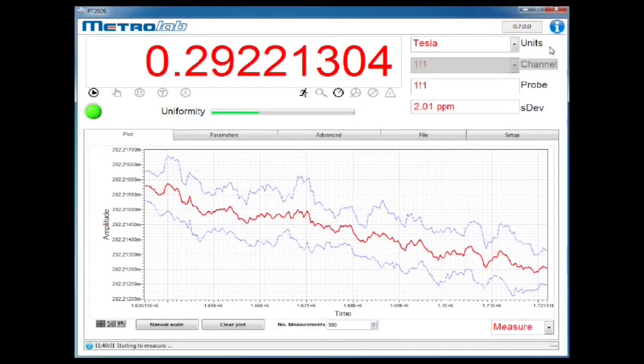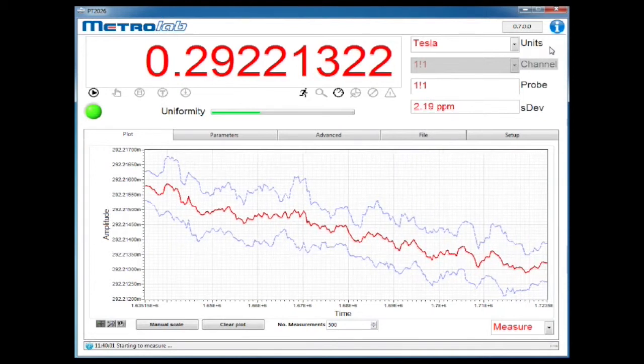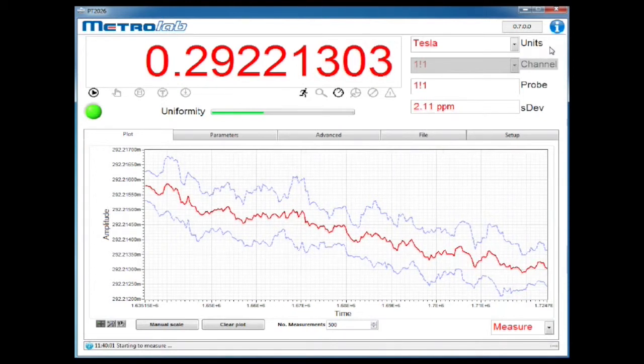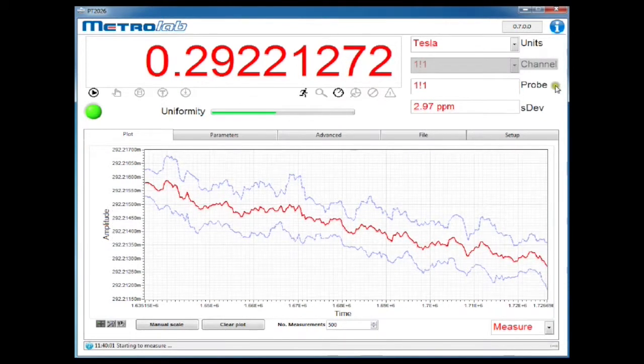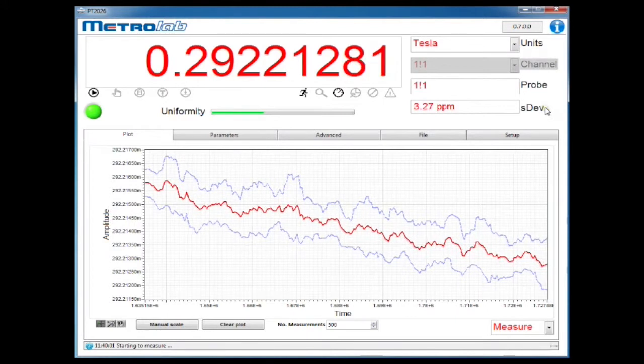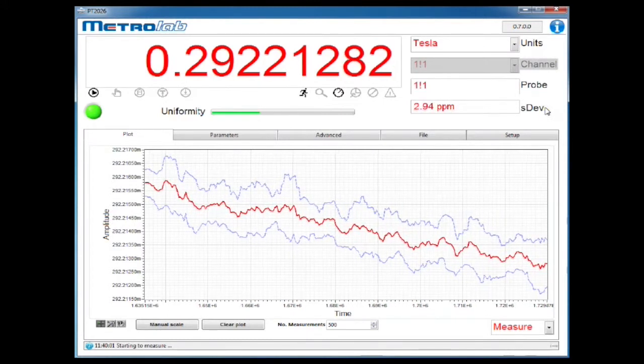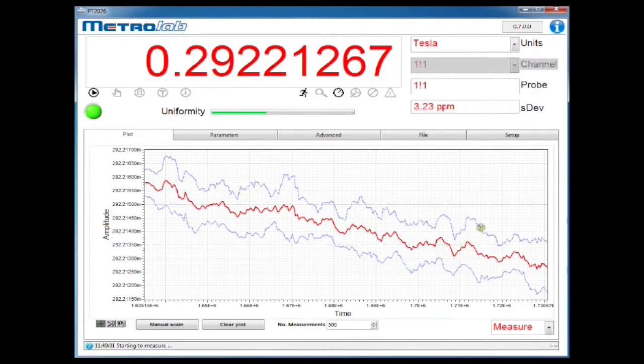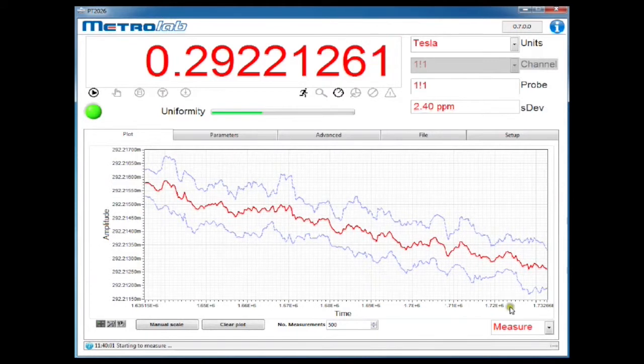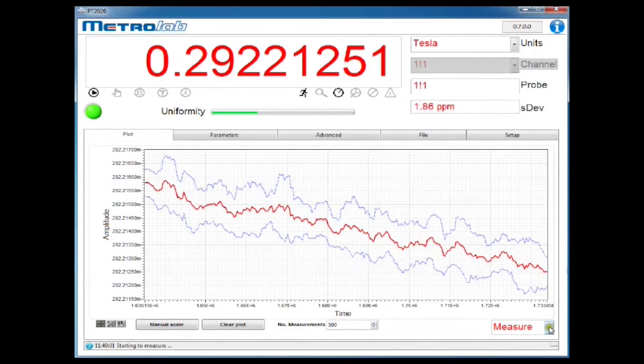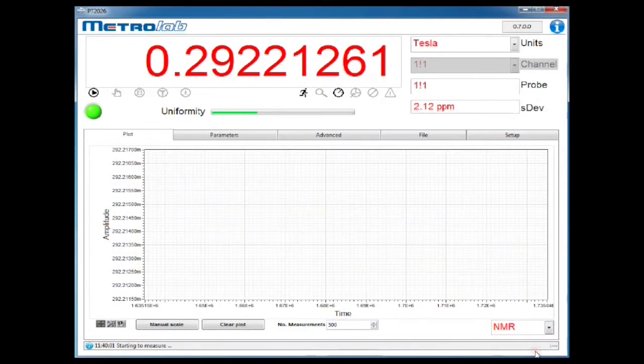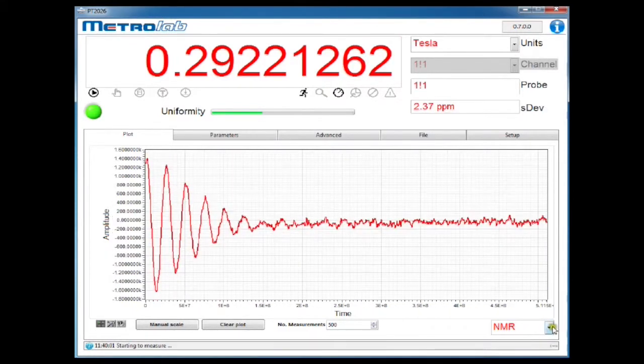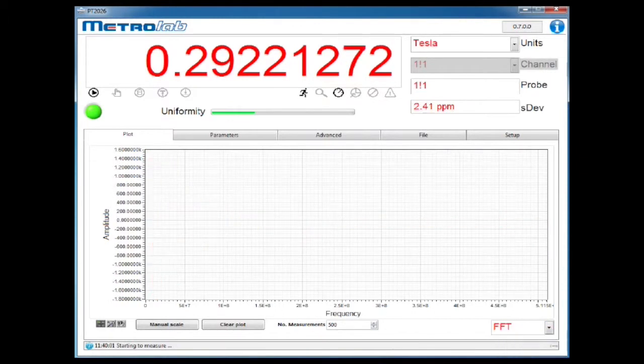The main screen shows the flux density in the units of your choice, textually as well as on a strip chart display. If you've selected measurement averaging, you'll also see standard deviation of the measurements, shown as error bars on the plot. You can also display the NMR signal, or the spectrum showing the NMR resonance peak.